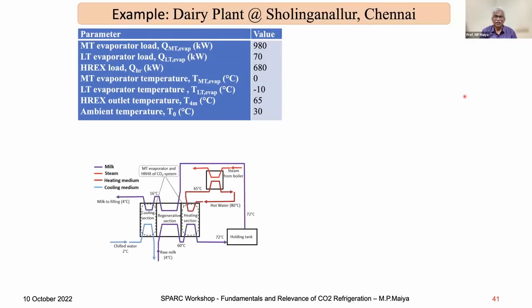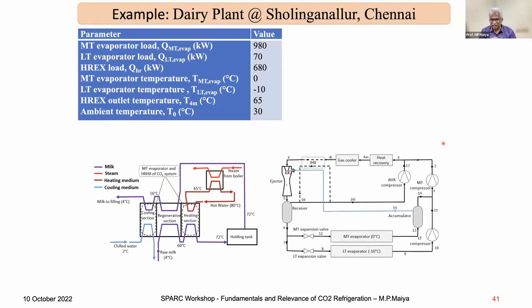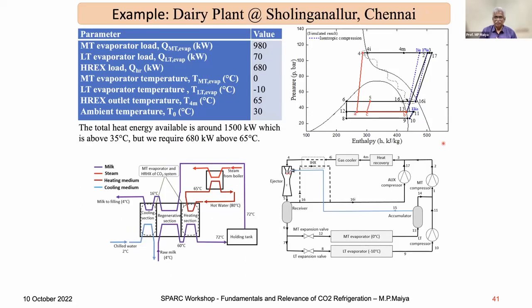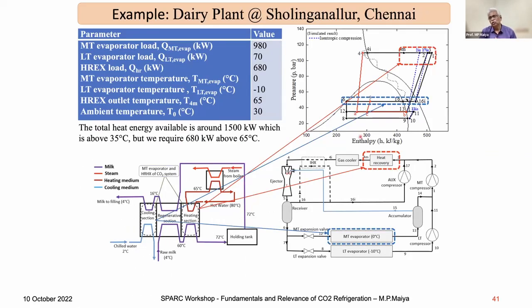Dairy application, you can see pasteurization of milk. It requires heating and quenching, cooling quickly. At present we use an ammonia chiller with brine for cooling, and a furnace oil fired boiler. So we can use this carbon dioxide system, and all these things can be accommodated, with both heating and 2 evaporators, one low temperature evaporator for butter storing and things like that. Heating is also used for cleaning purposes. So milk dairy is another application.